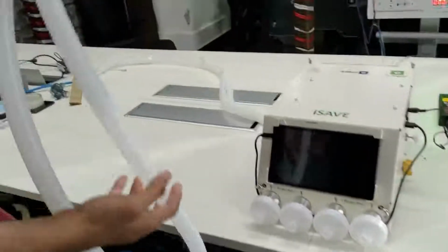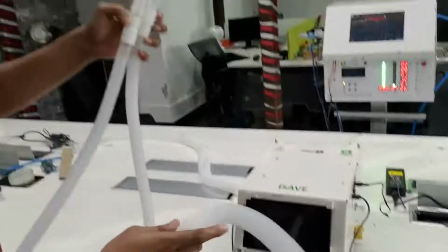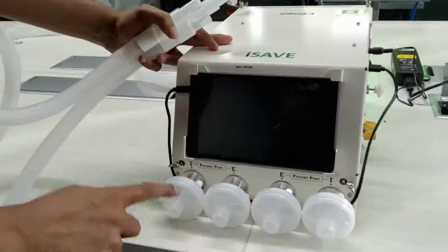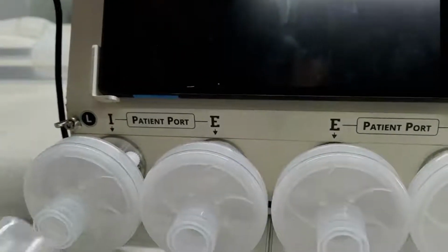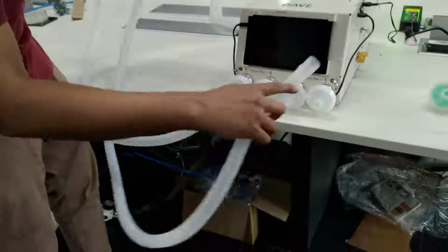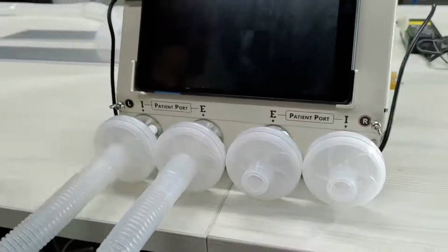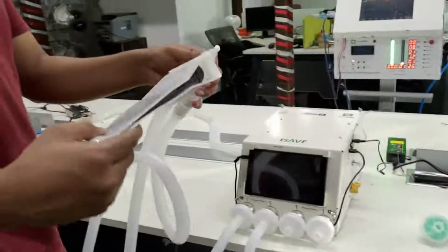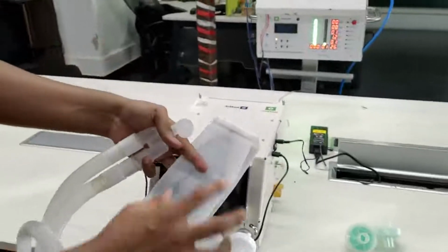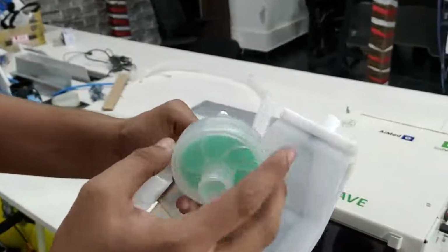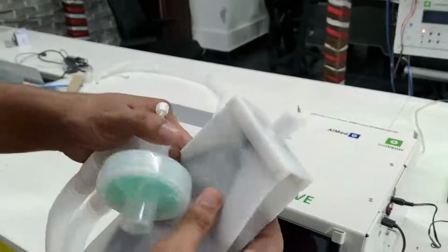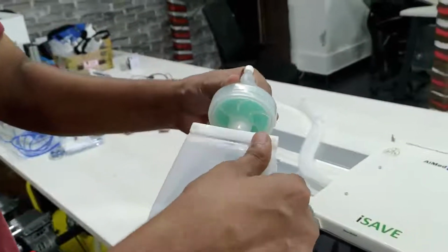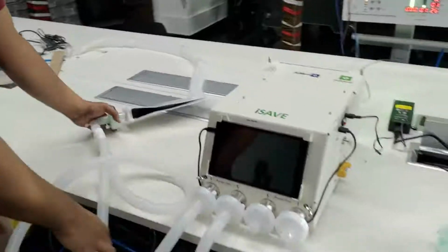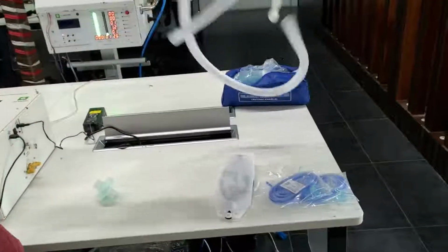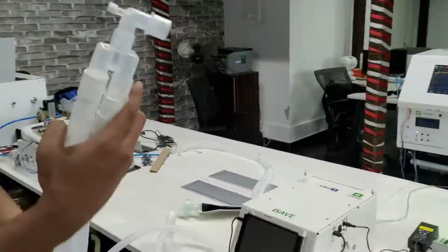So again, this is the inspiratory port for the patient. So we connect to the inspiratory port of iSAVE. So this is inspiration. It's marked here as I. So this is the left patient connection for inspiration, and this is the left patient connection for expiration. Okay, and let's also connect up the artificial lung. Before we connect up the artificial lung, we need to make sure we put on the HME filter on the proximal side. Make sure it's capped. We connect it to the artificial lung. Let's put that to the side. Similarly, let's connect up the right patient. So again, inspiration connection here, large to small valve.